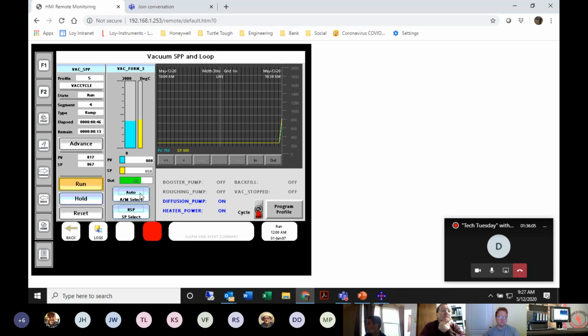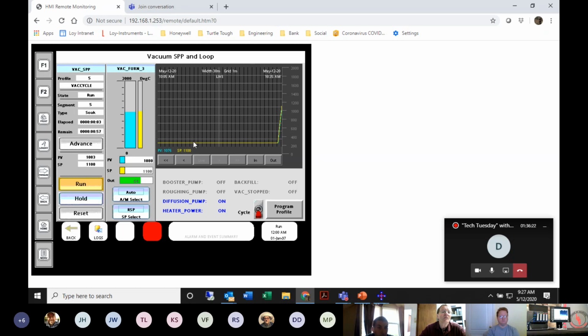You have your auto manual button, and then your remote select set point button along with the bar graph. So this actually gives you all of the indications that you would typically have, except for the bar graphs, on the front face of a UDC. And we've added a couple more things on this display. We've added a profile trend display on the right-hand side, along with a set point programmer, which actually mimics a DCP programmer that you would typically have on the front of the panel running the process.